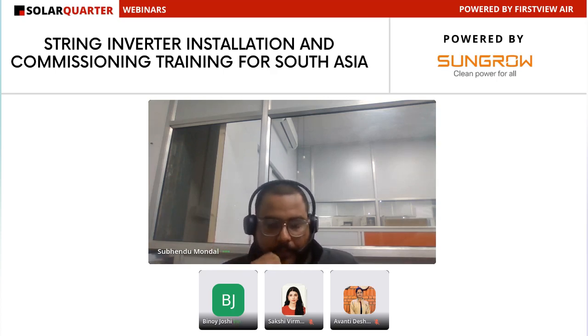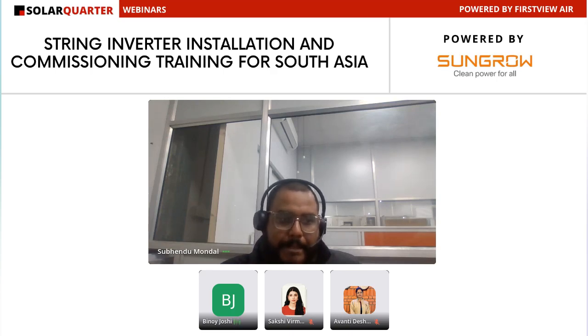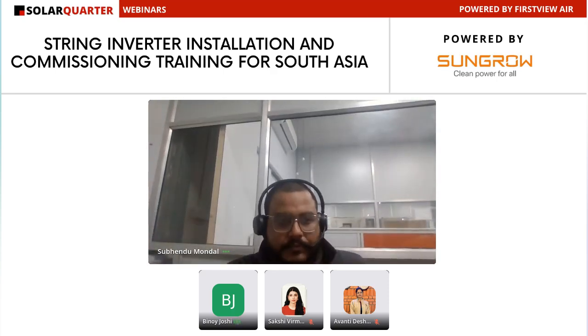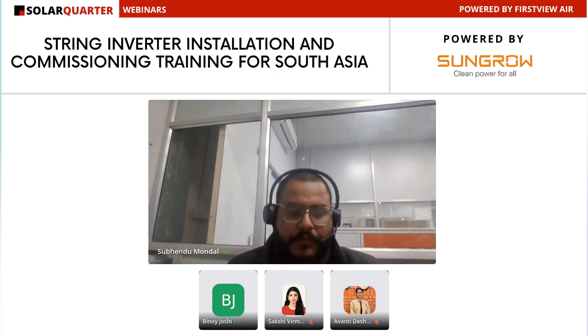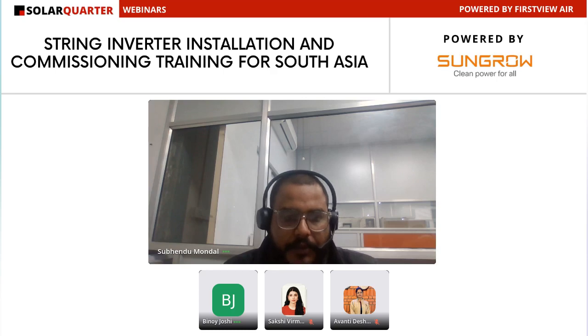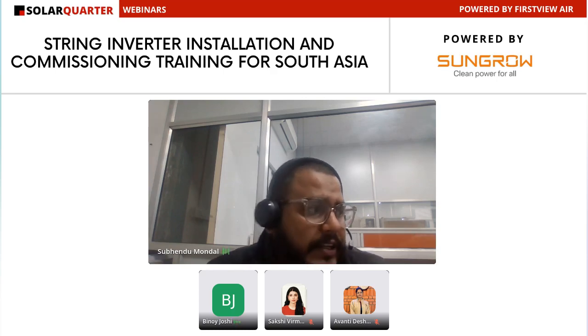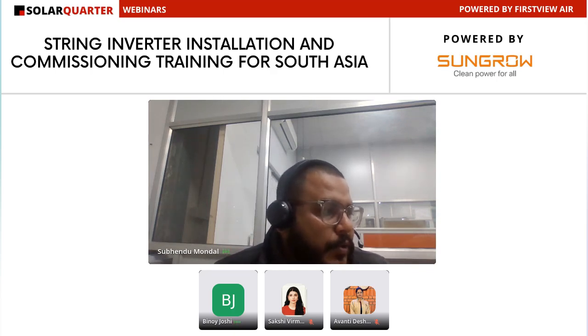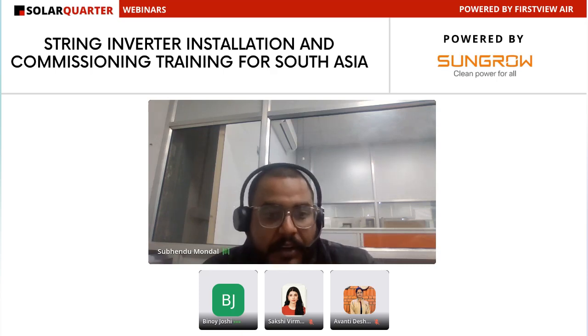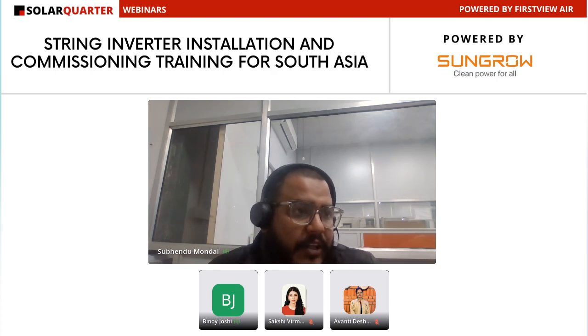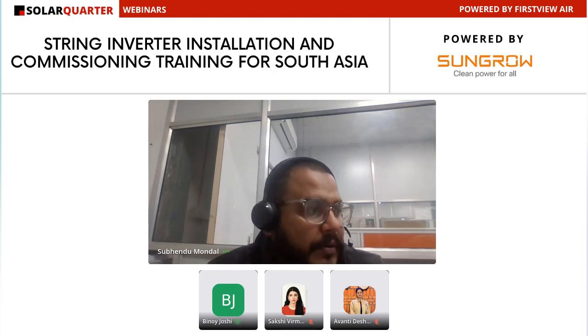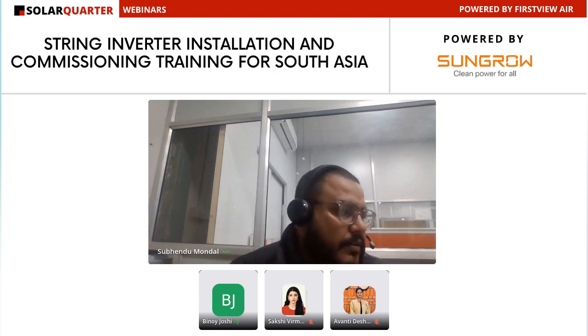So sir, how to rectify this issue? Because the government will come with a scheme to provide residential rooftop solutions to village consumers on a cluster basis, so this issue will come. Right now we are facing this issue. In this case, we have to check the cable length first, and the voltage drop. Use a high cross section copper cable to rectify this issue. But check with the discom, since the discom has already installed their cable up to the solar meter.